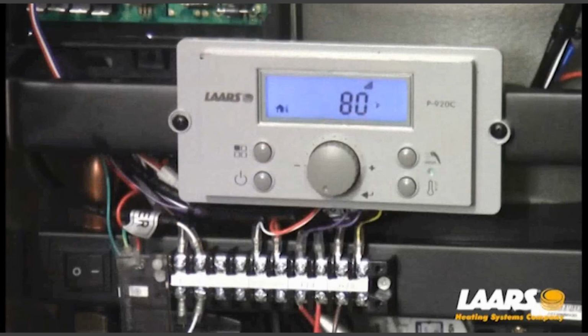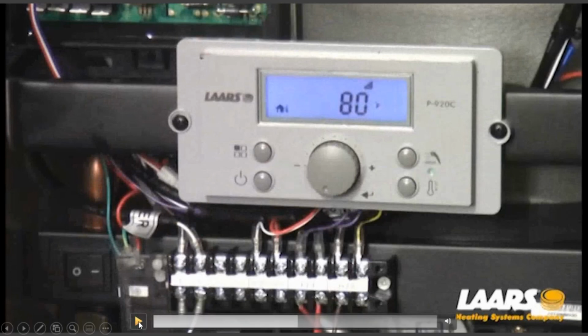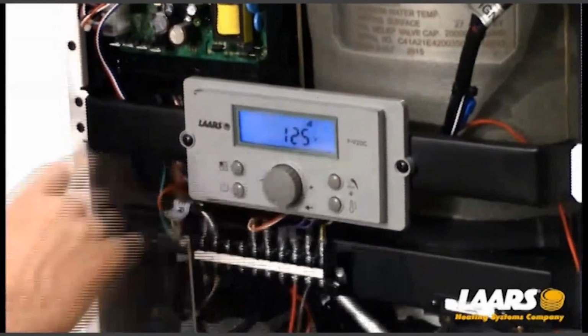Now, also, some states do require external mixing valves on the domestic side. And if you have an external mix and you want that set maybe at 120, you want to come in and elevate your internal set point, because we also have a mixing valve. You don't want them both set at the same temperature. You want your internal one running a little higher, so maybe 125, 130, or 135 in that example. So again, that can come as high as 140. I'll double check it by pressing the domestic button.